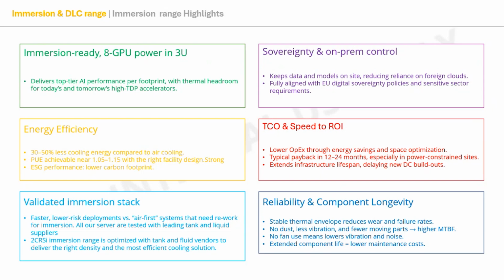In our new design, what we propose isn't necessarily very high density. Why? Because DLC can always do better than immersion. Also, in immersion, with these very hot chips we have now, gaining density isn't necessarily a big value anymore, because when the tank vendors say you can have 100 kilowatts per tank, yes you can, but you need very cold water.